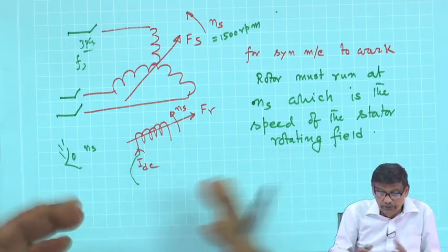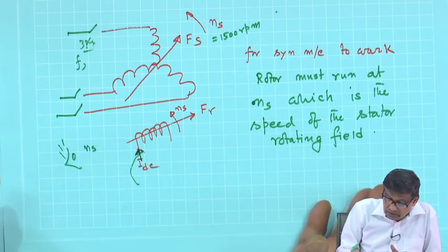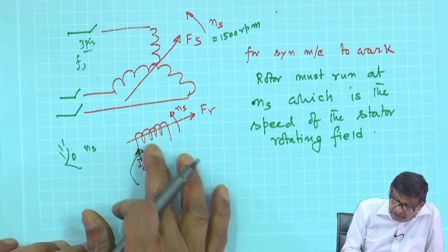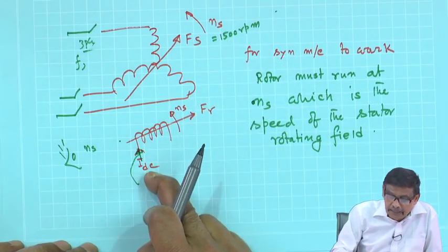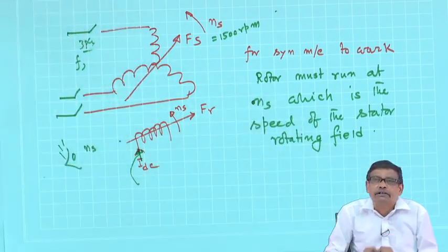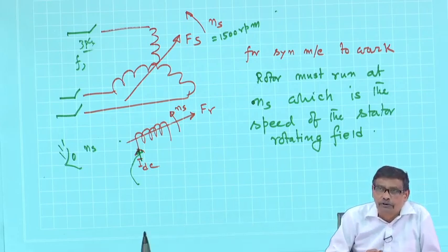Suppose it is a 4-pole machine with a 50 Hz supply — the stator field runs at 1500 RPM. I will excite the DC field, then use an external agency to bring the rotor speed up to 1500 RPM. Then I excite the field and close the switch — the machine runs fine, torque is produced which balances the load torque. These things can be easily understood without any mathematics.